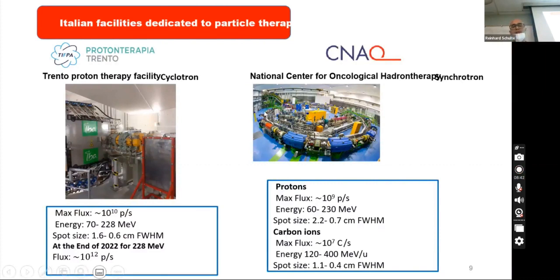The second center where we test our device is a national center for oncological hadron therapy, based on a synchrotron with a diameter of 25 meters, where it can accelerate both proton and carbon ion. The proton can reach a maximum flux of 10 to the 9 proton per second with the energy between 60 and 230 MeV. Instead, for carbon ion, the maximum flux can reach 10 to the 7 carbon per second with the energy between 120 and 400 MeV per nucleon.